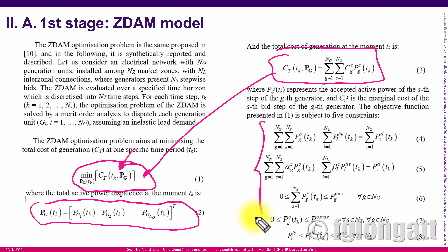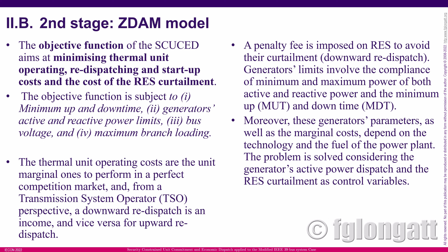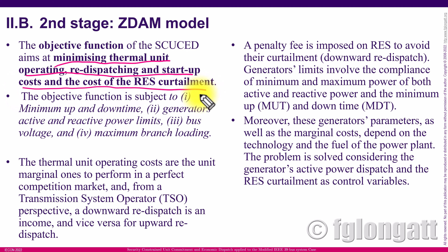The second stage of the proposed method has an objective function that minimizes the thermal unit operating redispatch and start-up costs, and also minimizes the curtailment of renewable energy resources. This objective function is subject to four constraints: minimum up and down time, generator active and reactive power limits, bus voltages inside limits, and maximum branch loading. This formulation includes the interest of the classical perspective of the transmission system operator regarding downward redispatch.